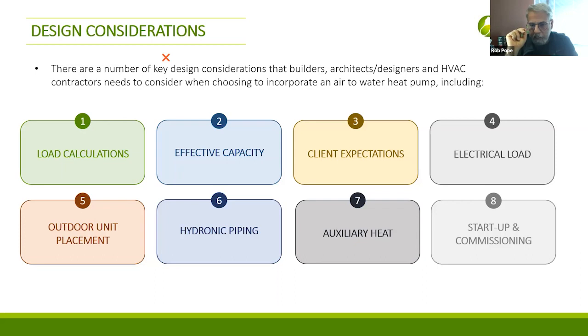Auxiliary heat - this is about the electrical panel, for one. How much electrical heat you need for backup if you're not using a dual fuel system. You could have a heat pump sized to meet the demand for most of the year, except maybe 2-3 weeks, the coldest days of the winter, and then your backup heat takes over, which could be a gas boiler. But in a lot of cases, that's going to be an electric strip backup. That's when your auxiliary heat is an issue, because that electric backup takes a lot of amps, and you have to make sure you're not overloading the panel.